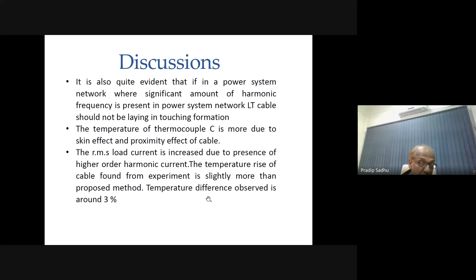From the life estimation calculation of the power cable, it is very clear that with the presence of higher order harmonics and the cable operating temperature increasing by around 3 degrees centigrade, the effective life of the power cable is reduced by 2928 days. It is not a matter of joke. These results are taken from the manufacturer data sheet of the cable. If there is a 3 degrees centigrade temperature rise, the lifetime of the cable will be shortened. Do you agree? Yes, sir.